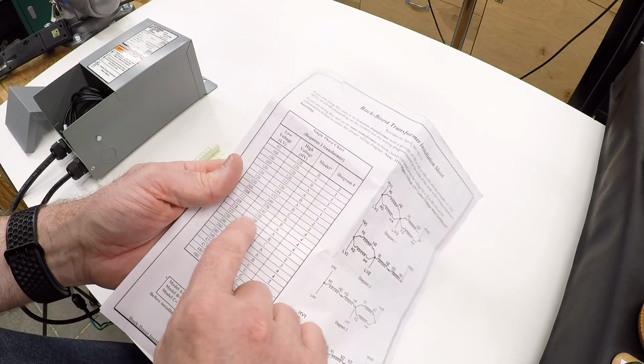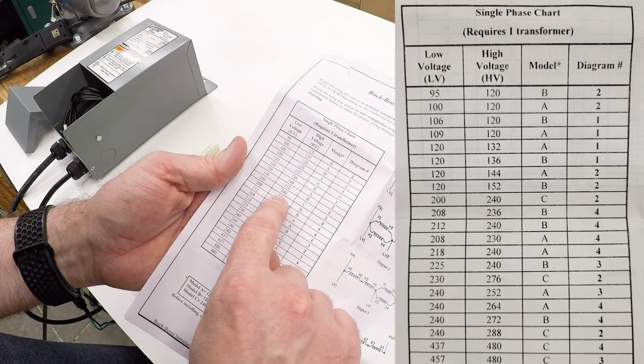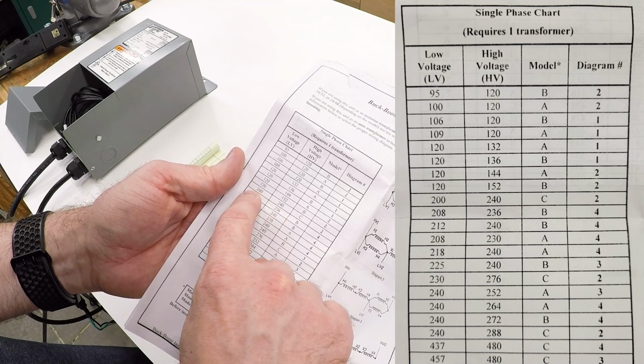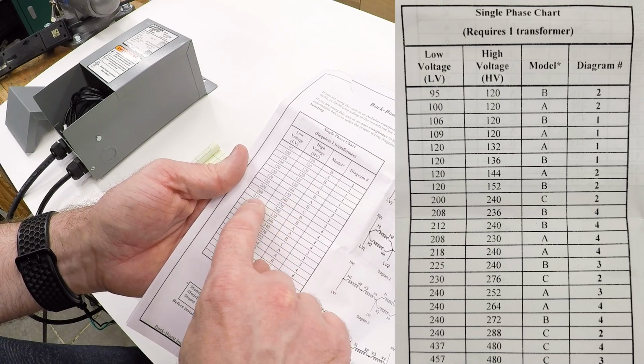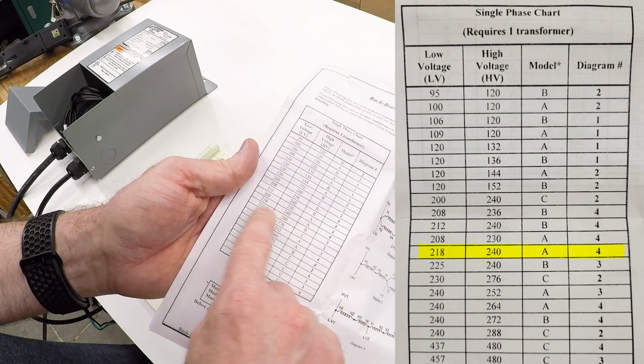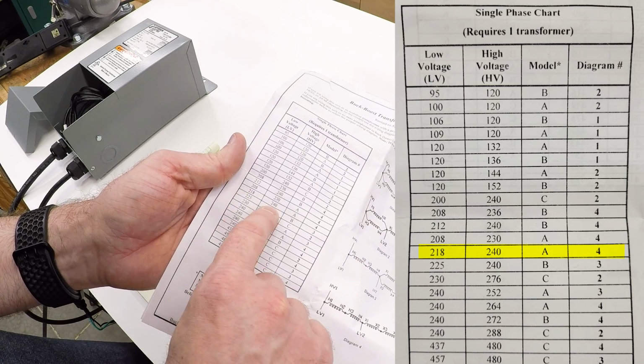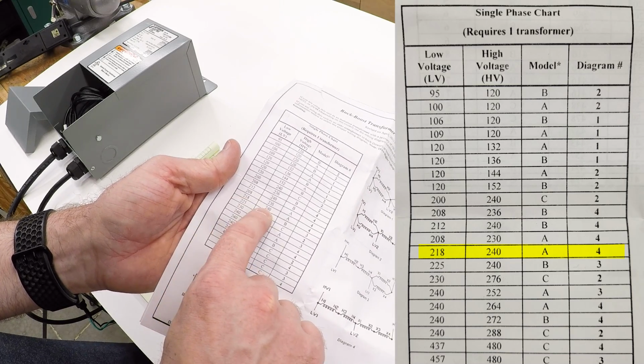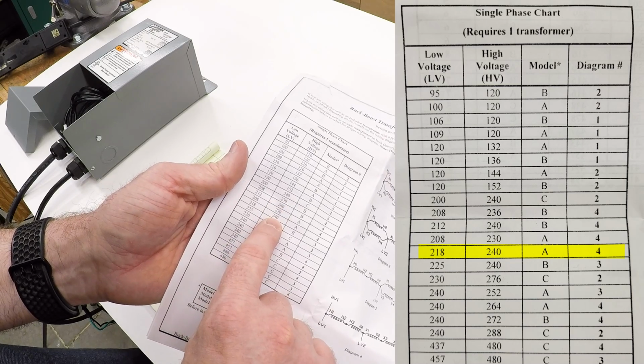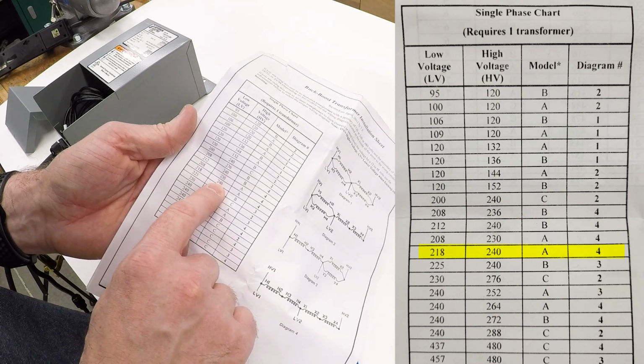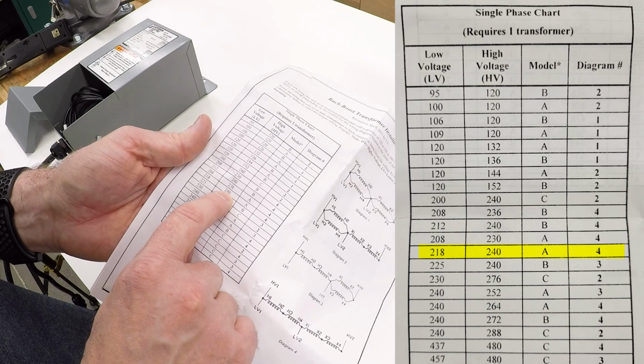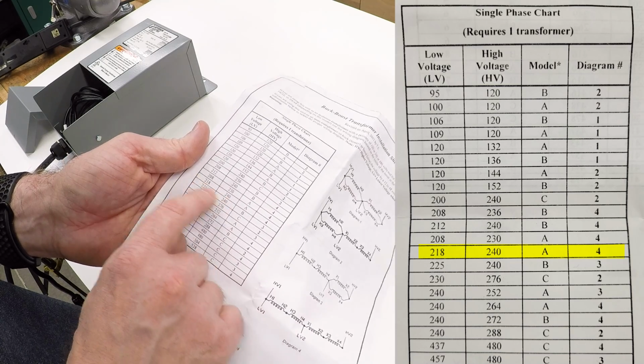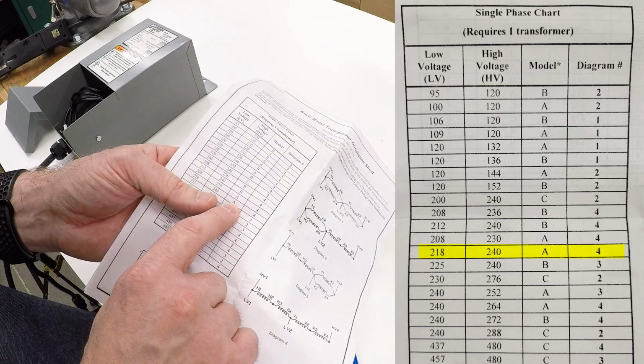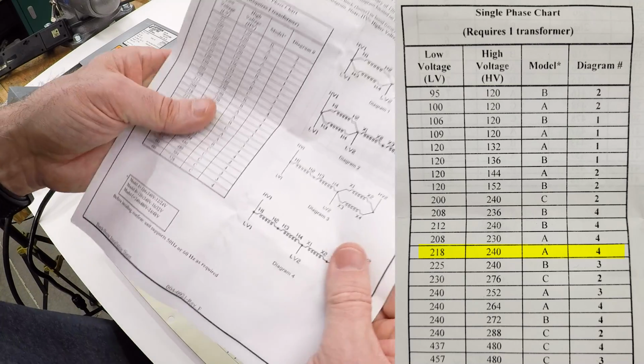Looking down this chart: on the high voltage side, 240 step down to 200 -- not what I want. 240 to 212 -- no. Here, 240 to 218 -- that sounds really good, and I could step up from 218 to 240. Since I have 244 volts and want to go to 220, this ratio is about the same. That's what I want: model A, which is the transformer I have, diagram 4.